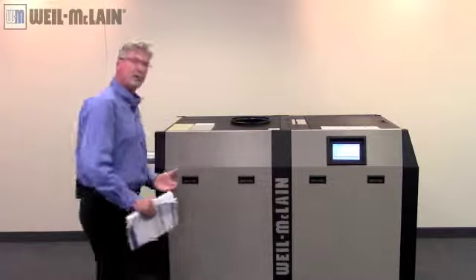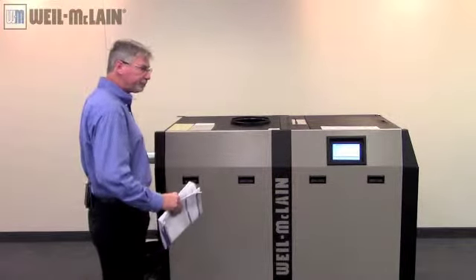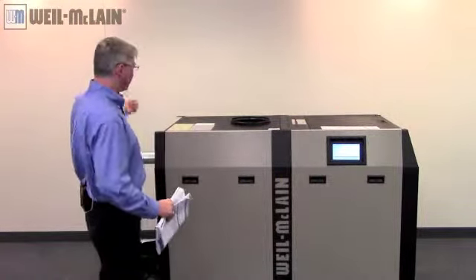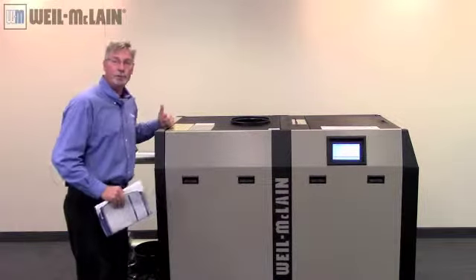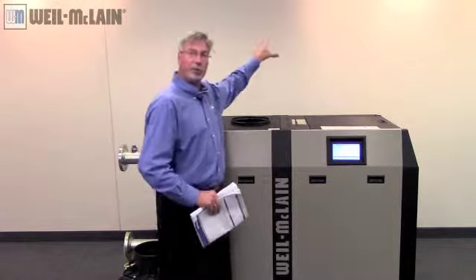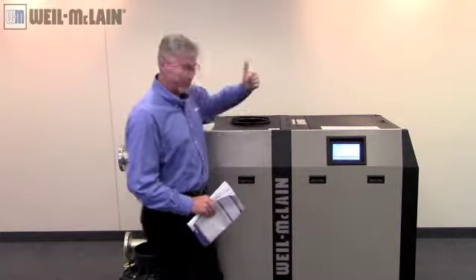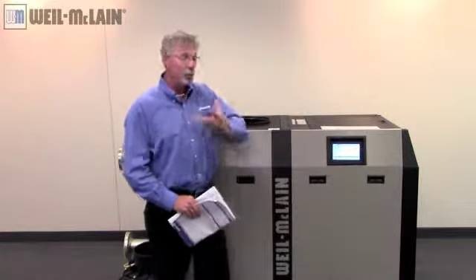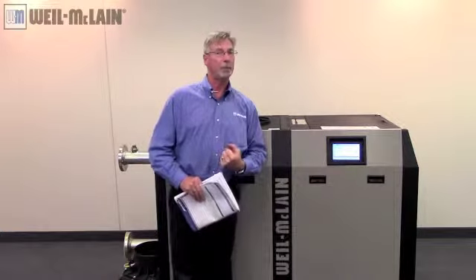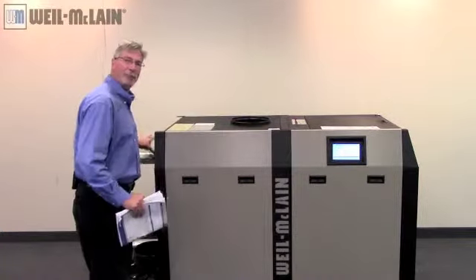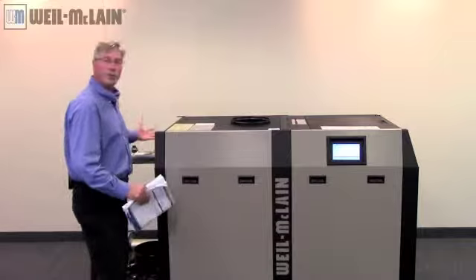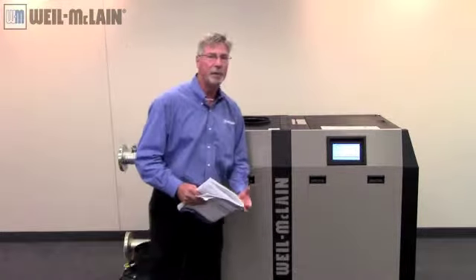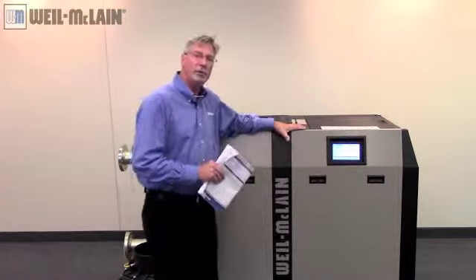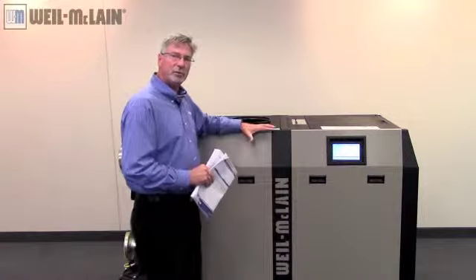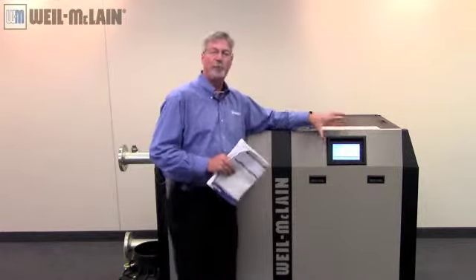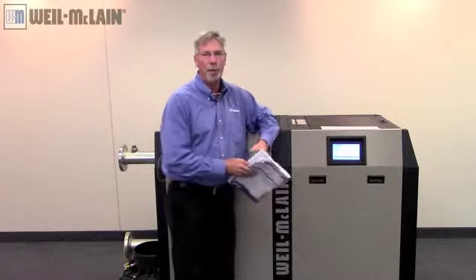Now, if your boiler return temperature is somewhere around 180 degrees and your supply temperature is 200, and your system temperature is 140, you're telling me that you're not moving water through the boiler. You don't have any of that return water coming back. So now you can take a look at what's going on with the piping. Is there an issue with the circulator? Is a flow check stuck? So you see where I'm getting at with that? So be sure you do your due diligence, check all the basics, take a look at your temperatures, and a lot of times that is going to tell you where your problem lies.